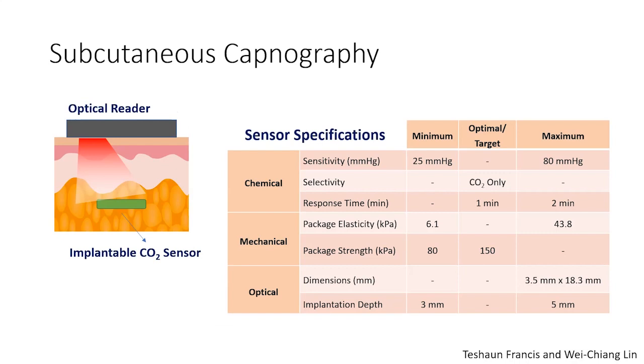So the cartoon on the right-hand side illustrates the device that we built to measure interstitial CO2 level. It has two components. One is an implantable CO2 sensor, and the other one is an optical reader. The implantable CO2 sensor is placed in the subcutaneous space and measures the PCO2 in the interstitial fluid. And then the response of the CO2 sensor is optically read by the optical reader on the tissue surface. So to build a system like this, we have to make sure of biocompatibility, that the sensor is sensitive to CO2 only, and that the CO2 sensitivity is in the physiological range. So that's why we have specs. And to make the subcutaneous capnography work, this sensor has to have such qualities.